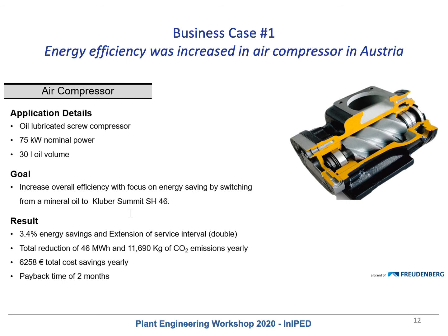The goal was to increase the overall efficiency with a focus on energy saving by switching from a mineral oil from a major oil company to a fully synthetic Kluber Summit SH46 oil, which is based on PAO, which is polyalphaolefin chemistry, or SHC, synthetic hydrocarbon, like we call it in the lubricant business. The result was a 3.4% energy saving and an extension of the service interval that doubled. That means less waste in the oil and also more equipment availability in service hours.